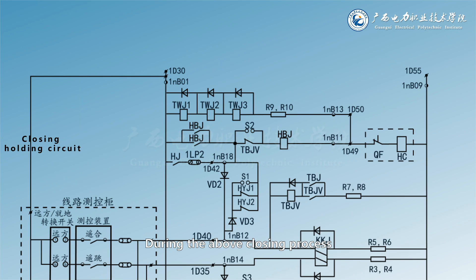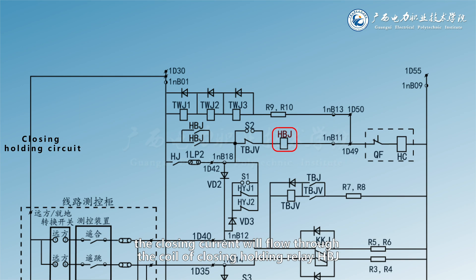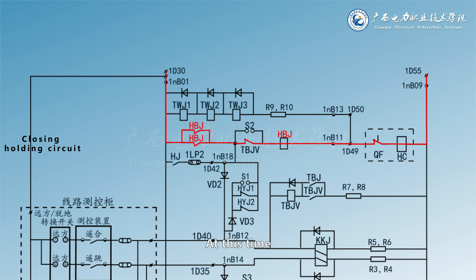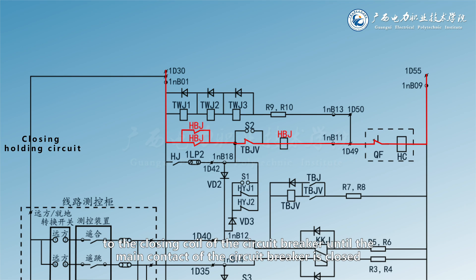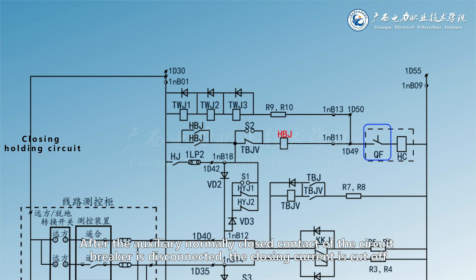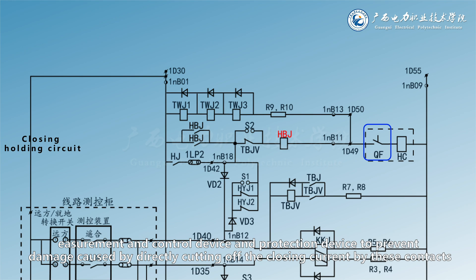During the above closing process, whether manual closing or automatic REC closing, the closing current will flow through the coil of closing holding relay HBJ. Therefore, HBJ acts and self-holds by its two pairs of parallel normally open contacts. The closing current can flow from the two pairs of parallel normally open contacts of HBJ to the closing coil of the circuit breaker until the main contact of the circuit breaker is closed. After the auxiliary normally closed contact of the circuit breaker is disconnected, the closing current is cut off, so as to ensure the reliable closing of the circuit breaker. At the same time, it also protects the contacts of the local operation switch, measurement and control device and protection device to prevent damage caused by directly cutting off the closing current.